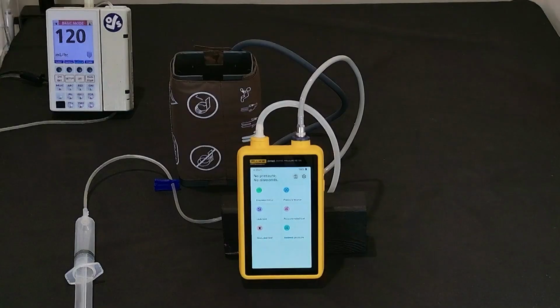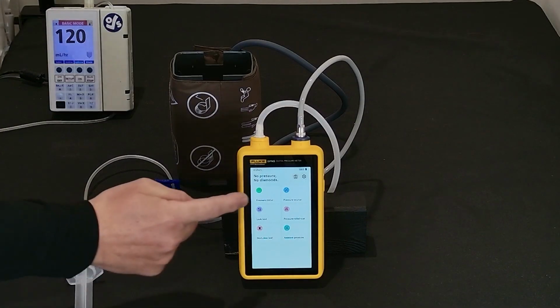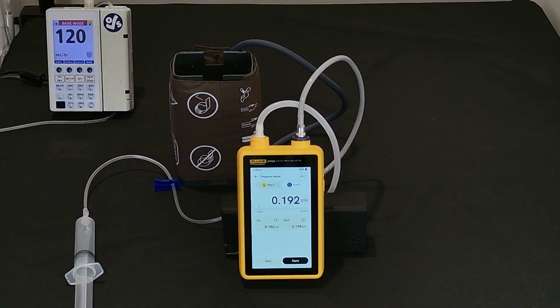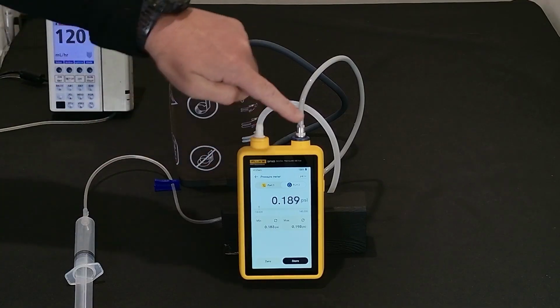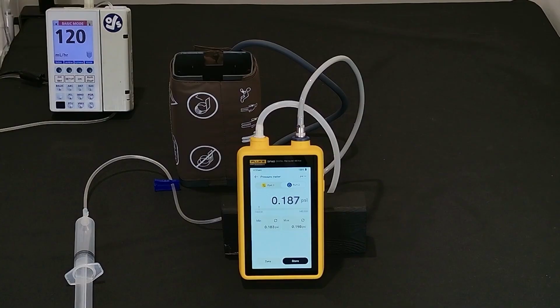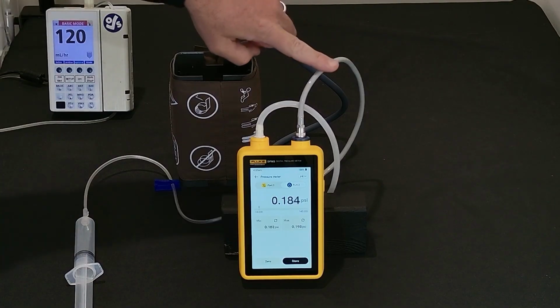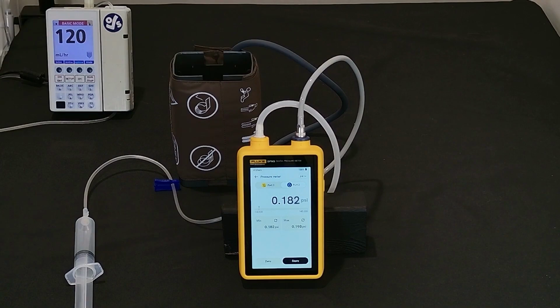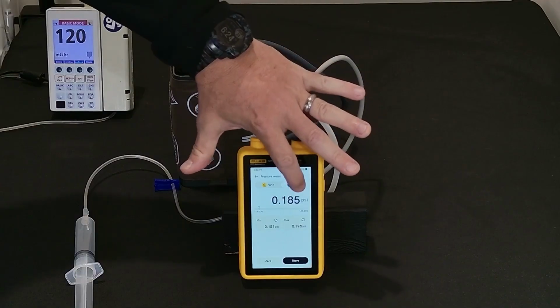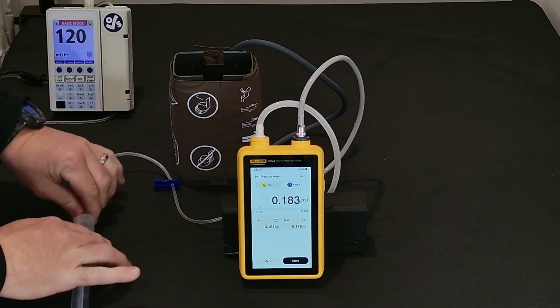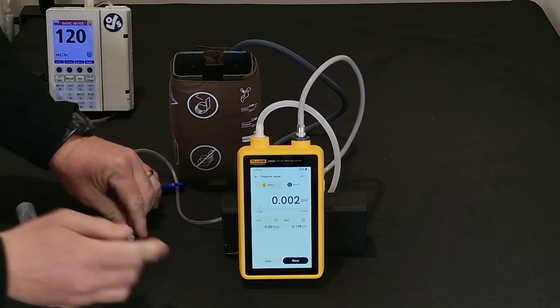From the home screen, you'll see there's 6 apps. First, look at the pressure meter. We'll select pressure meter, and then here you have the option of port 1 or port 2. Port 1 is for dry, non-corrosive gases and for your pressure pump, and port 2 is for dry gases and liquid. So here we'll select port 2.